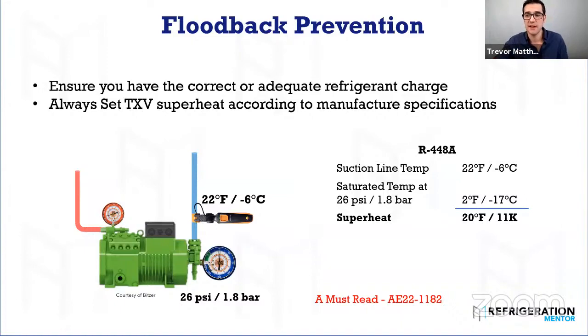So you need to look that stuff up and make sure you're checking that. Always maintain proper airflow, because if you're not boiling off that refrigerant or absorbing the heat in the evaporator, the fans aren't running, you've got honeycombs dirty, you've got evaporator plugged, you've got it iced up, you're going to run into a lot of issues.